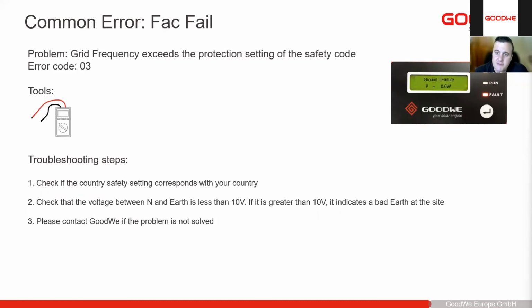FAC failure is very similar to VAC failure, except it's the frequency. Just make sure that our country's safety settings are set correctly. Sometimes with this FAC and VAC failure, we might just need to update our inverter, recommission it, and then the problem will be resolved as well. But we always need to double check and make sure the neutral and earth are correct and that all our cables are well connected.